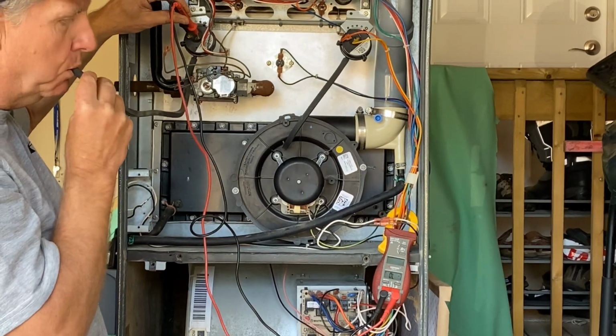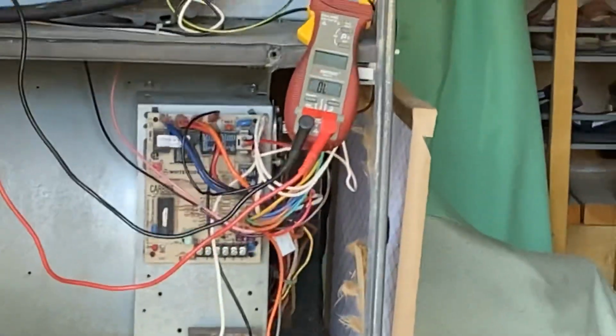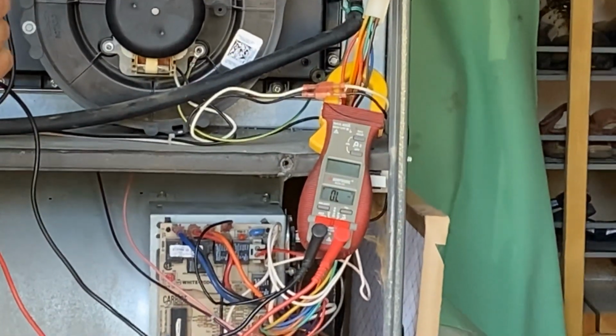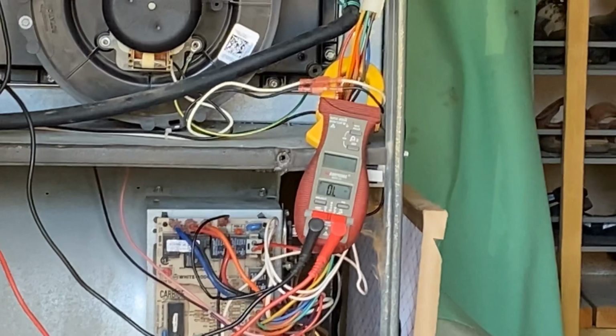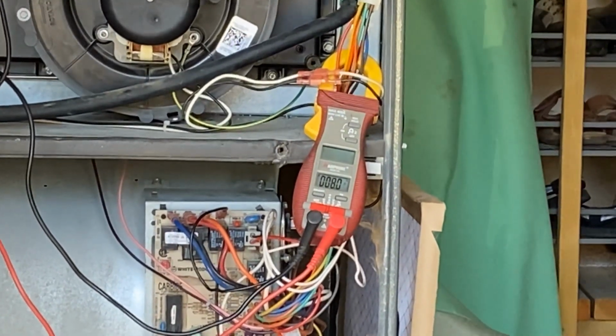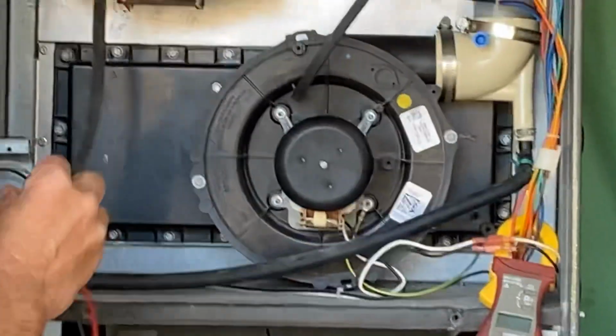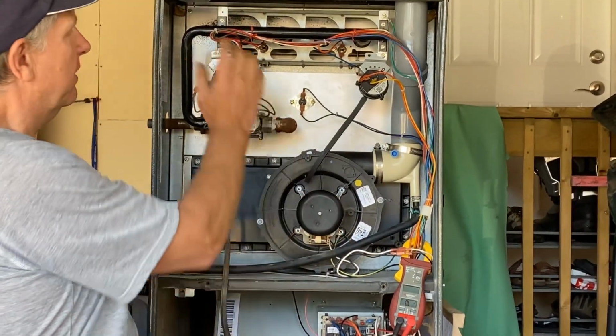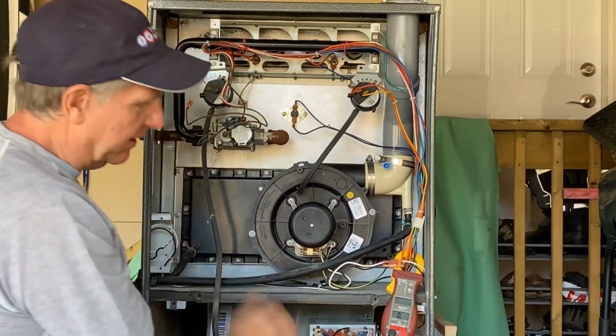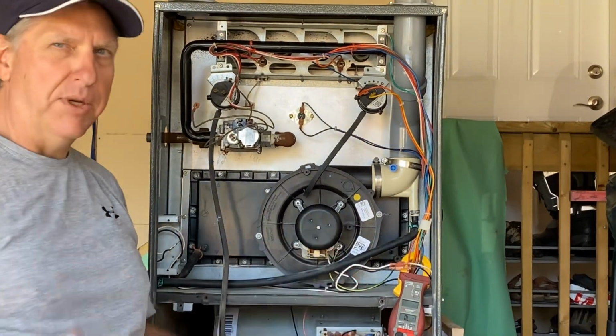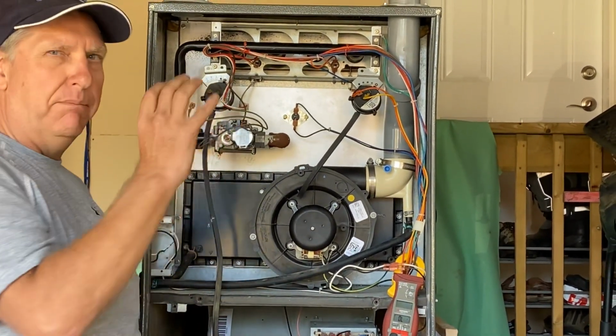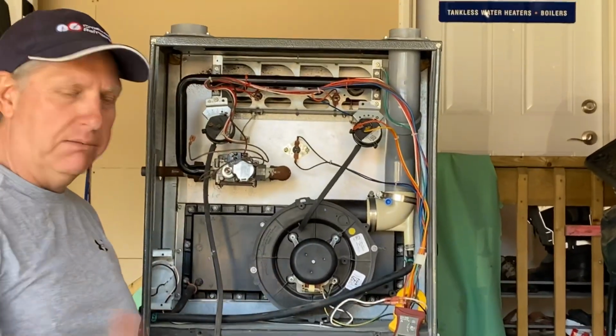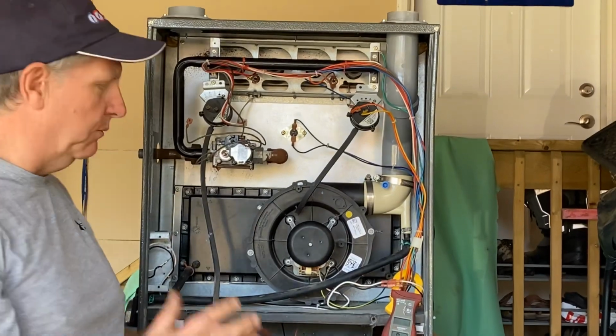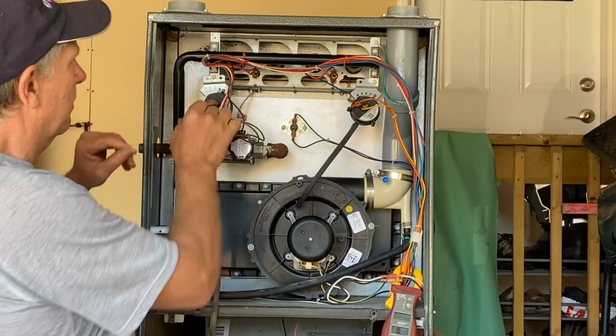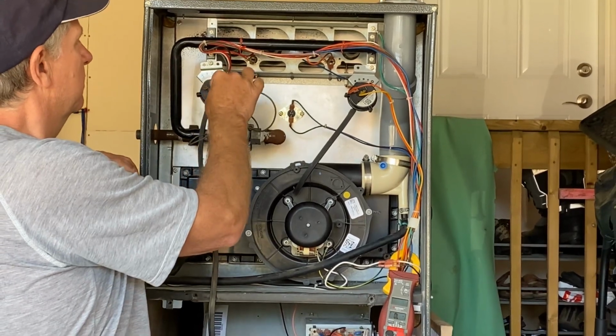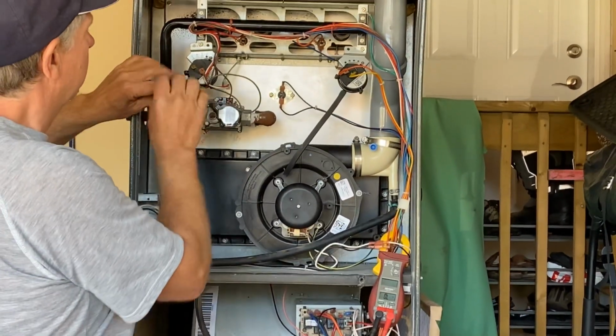If I suck on it, you can see that I actually get continuity. So as soon as there's some negative pressure, the switch closes, I have continuity. So as soon as this venter motor starts, these switches sense the negative pressure, send a signal to the circuit board saying everything's okay, we're okay to fire up. If they do not make a circuit, the circuit board will say, nothing's going to happen, something's wrong, we're not going to have a flame. That's what these switches do. So basically just an open-close switch, very simple.